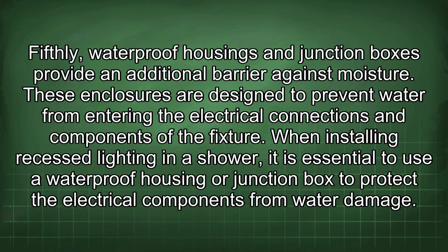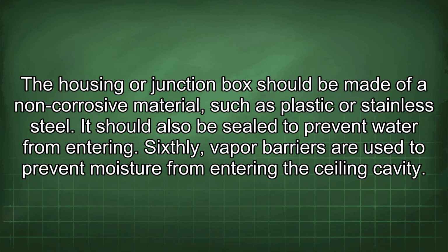Fifthly, waterproof housings and junction boxes provide an additional barrier against moisture. These enclosures are designed to prevent water from entering the electrical connections and components of the fixture. When installing recessed lighting in a shower, it is essential to use a waterproof housing or junction box to protect the electrical components from water damage. The housing or junction box should be made of a non-corrosive material, such as plastic or stainless steel. It should also be sealed to prevent water from entering.